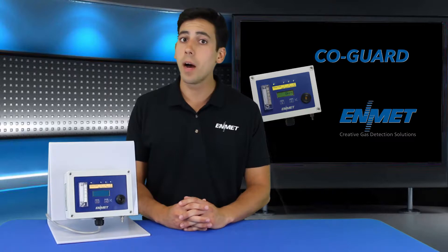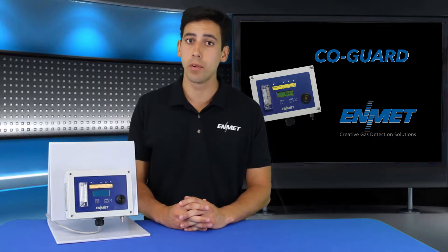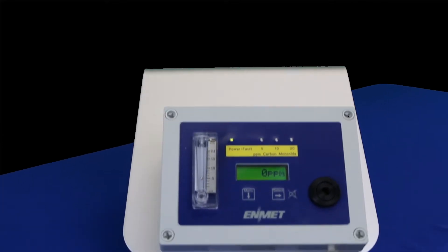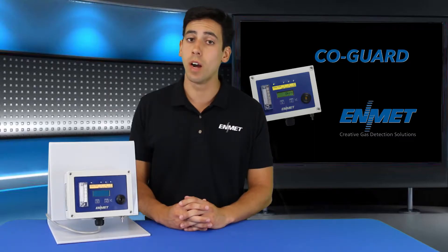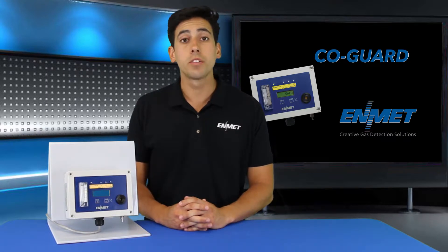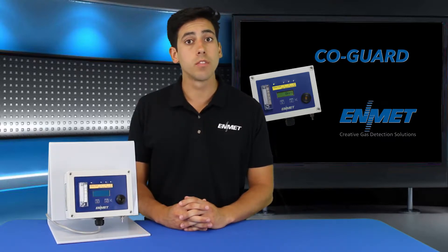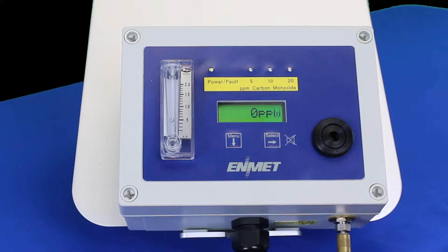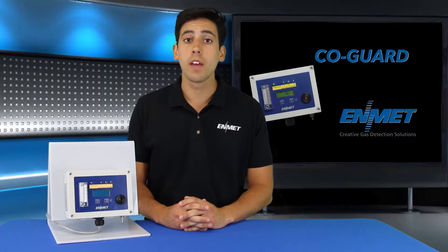The CO-Guard is a compact, easy to install and operate compressed airline carbon monoxide monitor that meets OSHA monitoring requirements for grade D breathing air. The instrument is specifically designed for trouble-free operation by utilizing a highly specific electrochemical CO sensor with a life expectancy of up to three years.